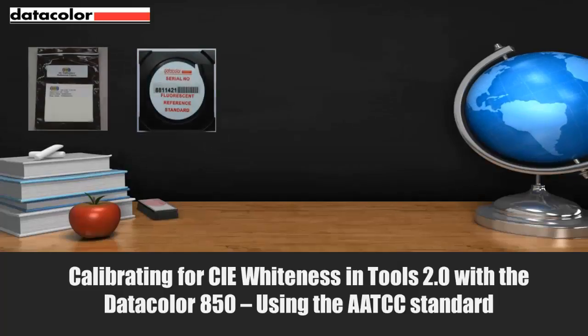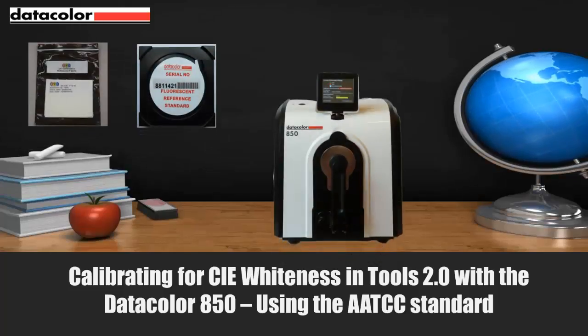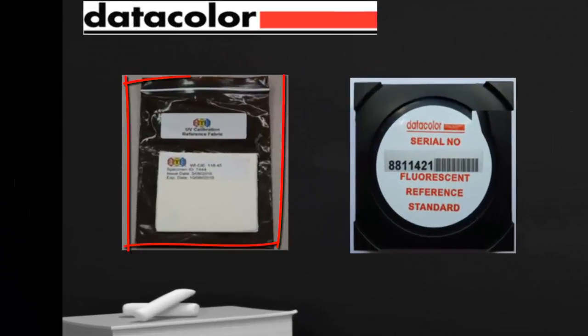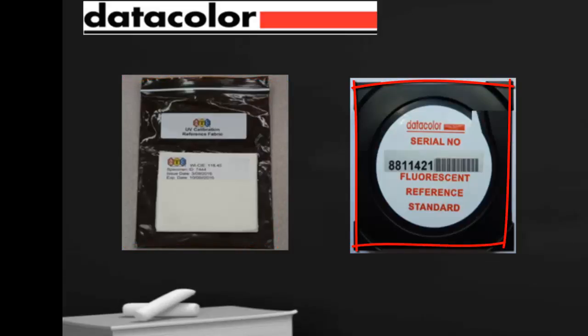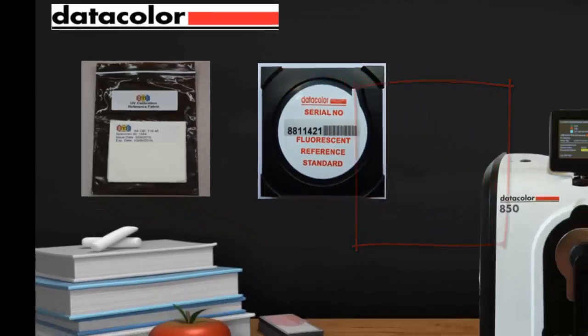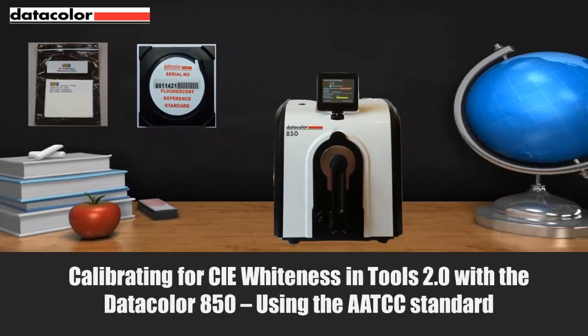In this video, we will present how to calibrate for UV with your spectrophotometer in Tools 2.0. We will be using the AATCC Standard for CIE Whiteness or the Datacolor Fluorescent Reference Standard Tile for CIE Whiteness. The CIE numbers for the Datacolor Reference Tile are standardized from the AATCC Standard. This is done with our UV Assured Maintenance Program.